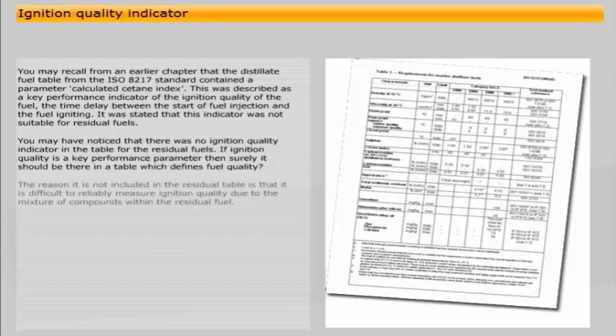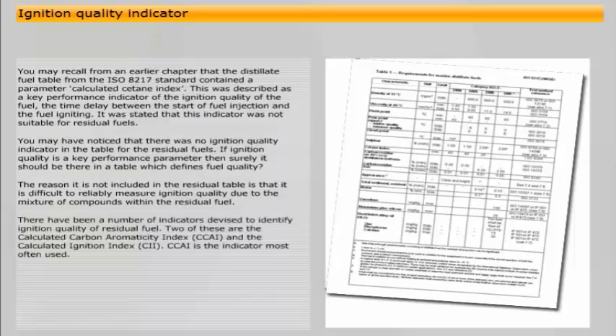The reason it is not included in the residual table is that it is difficult to reliably measure ignition quality due to the mixture of compounds within the residual fuel. There have been a number of indicators devised to identify ignition quality of residual fuel. Two of these are the Calculated Carbon Aromaticity Index, or CCAI for short, and the Calculated Ignition Index, or CII.